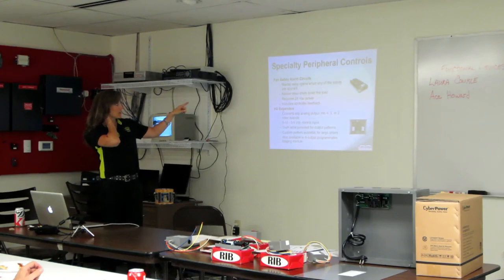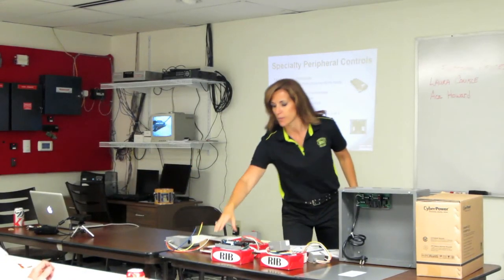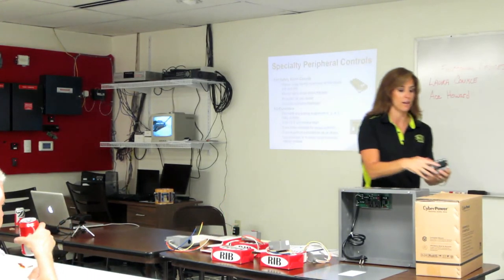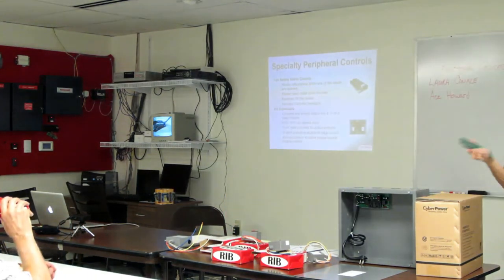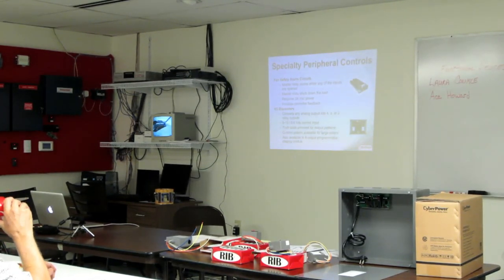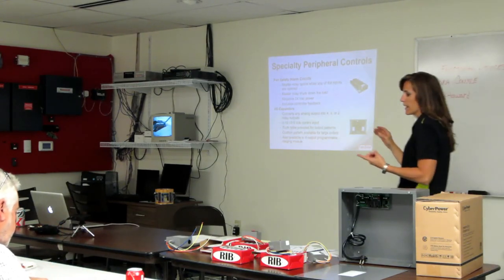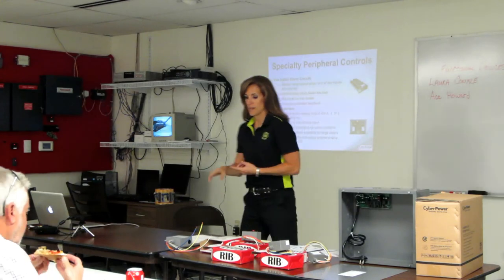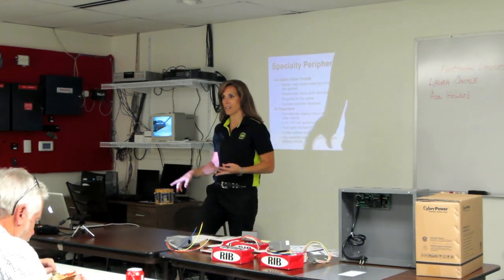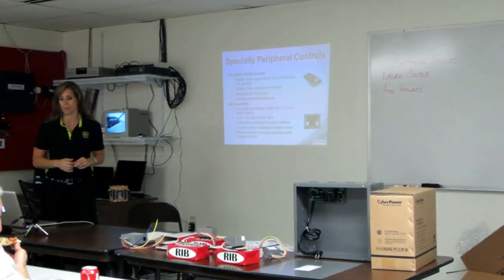Now our peripheral controls — the fan safety alarm. I did bring the R-I-B-M-N-L-B, that's this one right here. It's not attached to the track mount, but it does come with it. This is like your fan status relay. It has four inputs — three of them control your fan status, fan safety control, and static pressure. So it's like your safety alarm circuit.